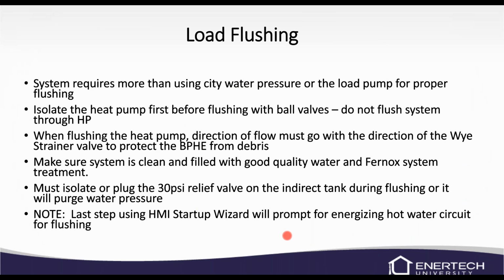We do require more than city water pressure for proper load side and source side flushing. So the load pump will not do it. You can try it, but it won't work, I can tell you that. Basically, I would recommend isolating the heat pump before flushing on a non-pressurized system, and don't flush through the heat pump. Whenever you do flush through the heat pump on a pressurized side of things, make sure that you're going with the direction of flow of the Y strainer. It's there to protect the braze plate. So if we were to go in the opposite direction, that first flush would force stuff into the braze plate. So make sure we're always going in the direction of flow through the heat pump.